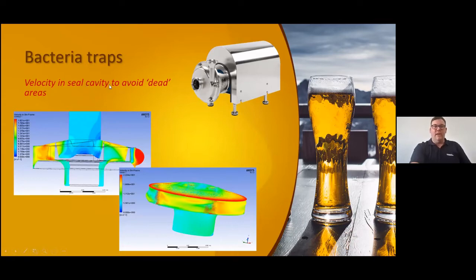Again, it's about the velocity in the seal cavity to avoid dead areas, so you don't want your mechanical seal to act as a trap for bacteria. It's important that the velocity of the pump and impellers create liquid movement around that area to stop dead spots and prevent your mech seal from becoming a bacteria trap.